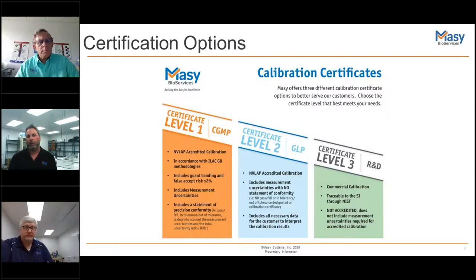Before I turn over level three to John, I want to say one quick thing. For me, even if I did not require an accredited CAL, I would still choose a vendor that offers accredited CALs. The reason is that all the hard work and infrastructure that goes into creating that accredited CAL, the quality system that has to be put in place, is still going to be used on your non-accredited calibration.